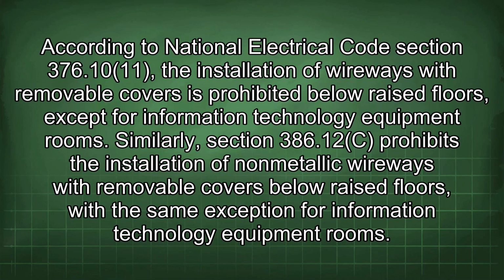According to National Electrical Code Section 376.10(11), the installation of wireways with removable covers is prohibited below raised floors except for information technology equipment rooms.